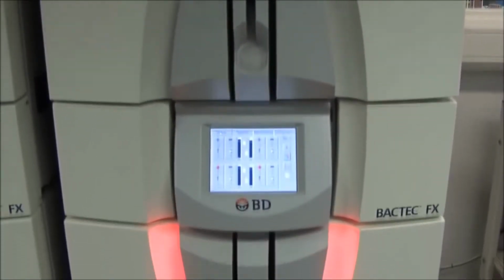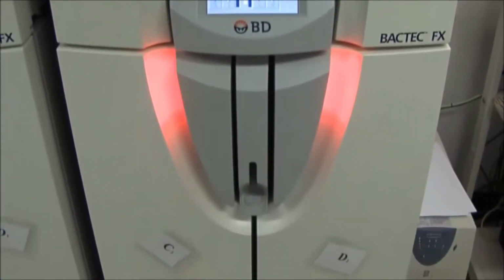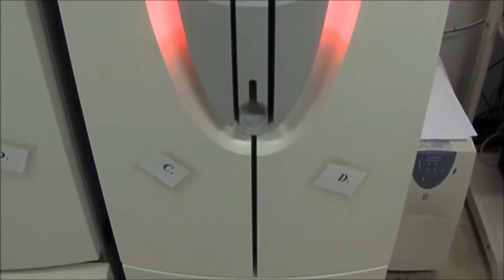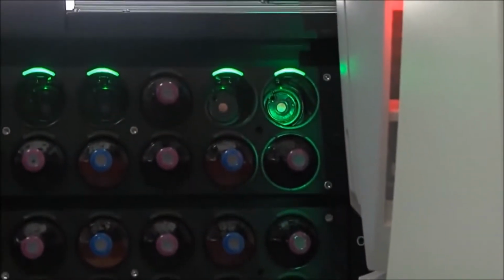It is an integrated piece of equipment consisting of an incubator at 35 degrees to allow optimum bacterial growth, an agitator, the bottle racks rock continuously, and a growth detector system built into it. Blood culture bottles are loaded onto the analyzer and incubated for up to 5 days.